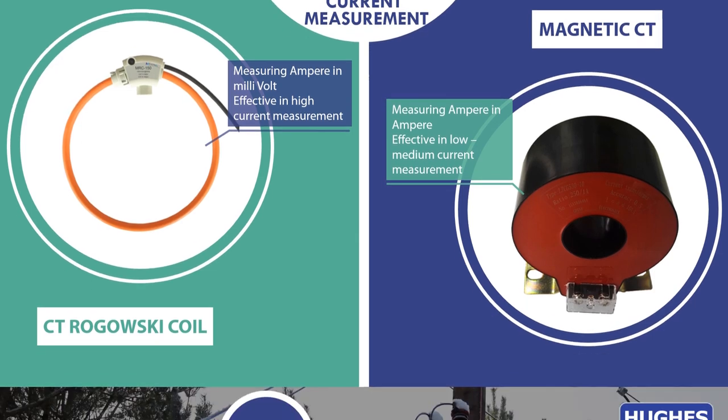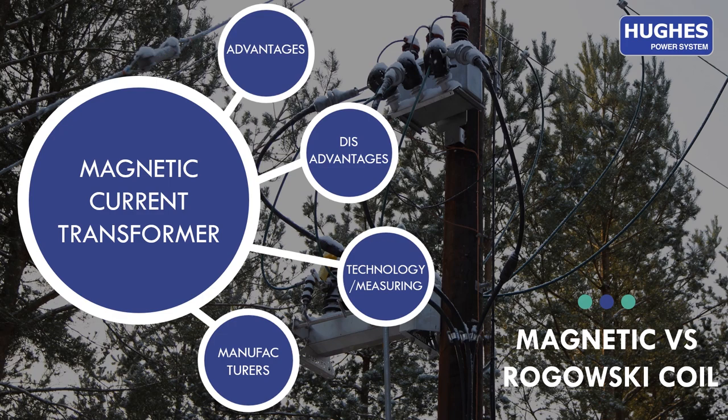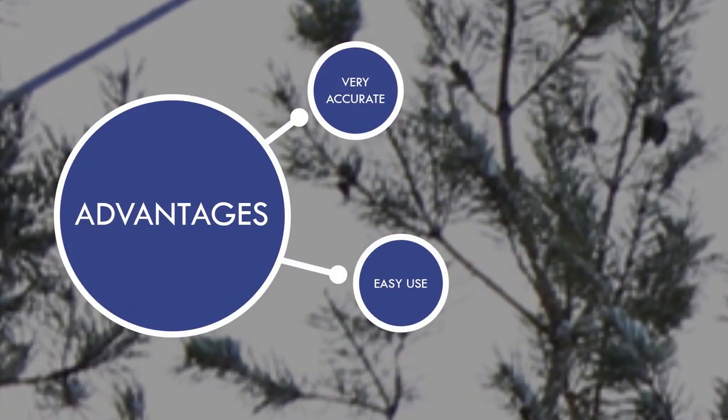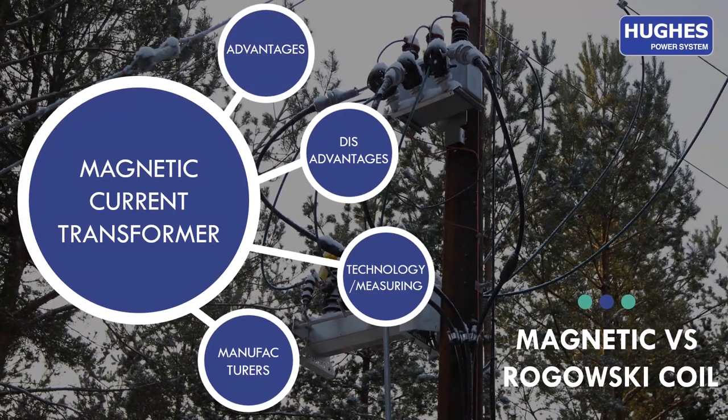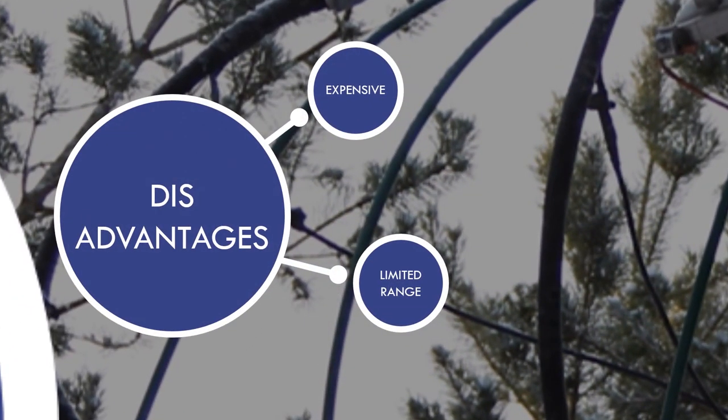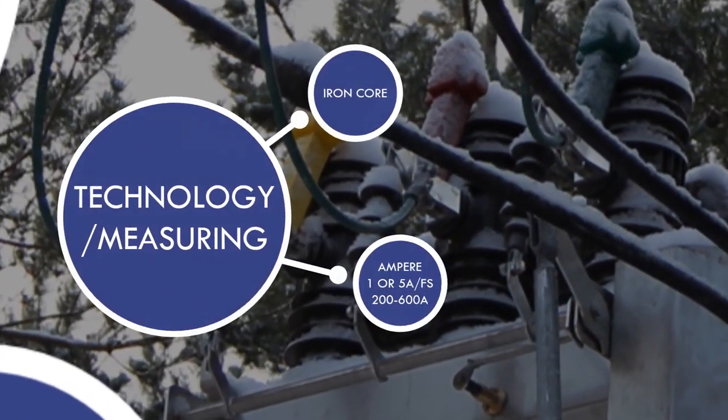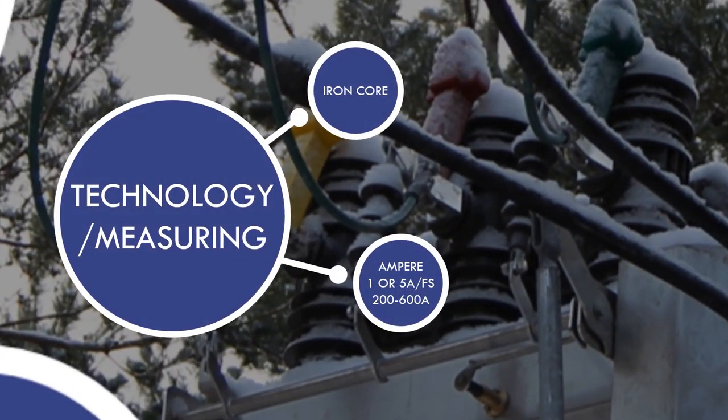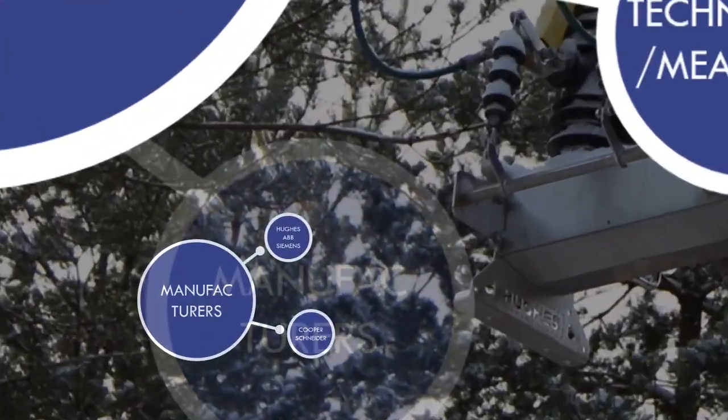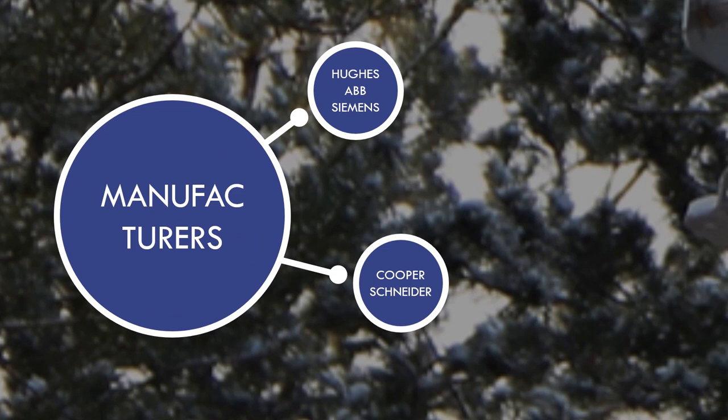Let's look at the parameters for both types. First is overview of a magnetic current transformer. Its advantages are very accurate measurement and easy to use. The disadvantages are that it is expensive and has a limited range due to its magnetic core. Next parameter is technology. Magnetic current transformer uses an iron core and output signal of 1 or 5 ampere. The manufacturers producing reclosers with magnetic current transformer include Hughes, ABB, Siemens, Cooper, and Schneider.